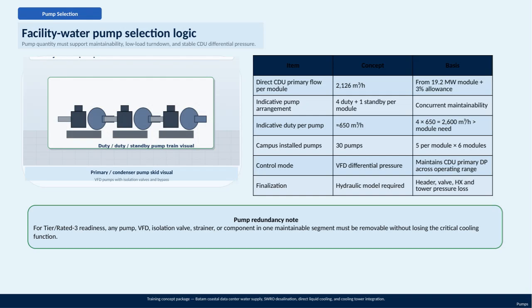Let's dive into the logic behind selecting the facility's water pumps. The key here is to ensure the pump quantity supports maintainability, allows for low load turndown, and maintains stable CDU differential pressure throughout operations. This balance is crucial for reliable and efficient cooling performance. Our training concept package covers the Batam Coastal Data Center's water supply, integrating SWRO desalination, direct liquid cooling, and cooling towers. When we look at the pumps themselves, the primary or condenser pump skid includes VFD pumps equipped with isolation valves and bypass lines, allowing for flexible control and maintenance.